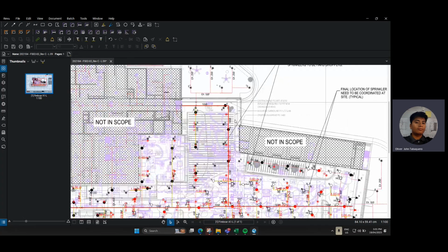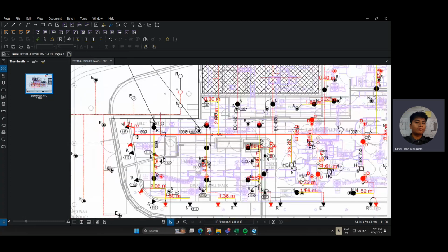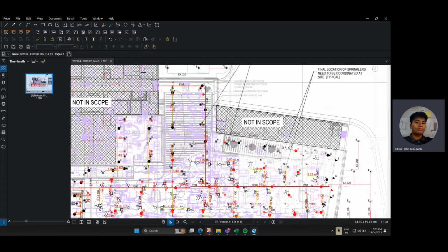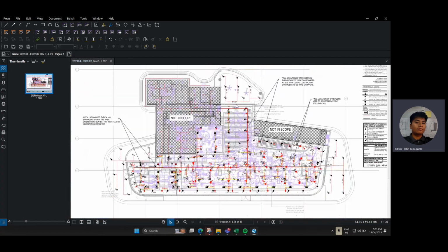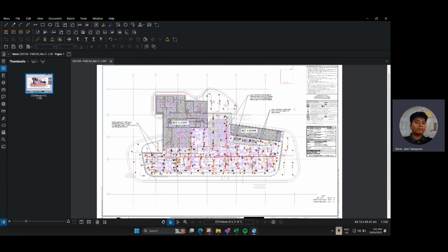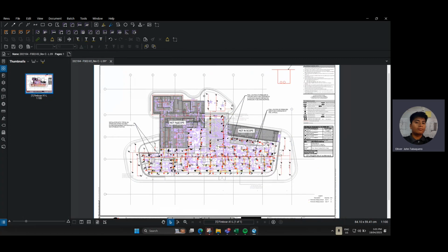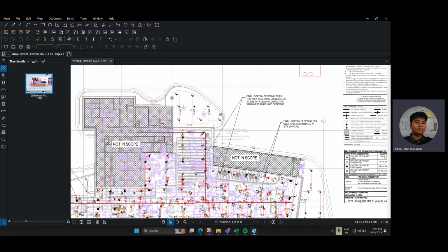So essentially, as we've discussed, you would just measure all of the lengths of this fire project. For design purposes, in the design discipline, we would always take into consideration all of them unless they say that it's directly fixed. For fire pipes, either it's directly fixed or it's not. If it's not directly fixed, we will restrain them. If it is, then we don't have to consider them. So that's essentially the rule for fire pipes.